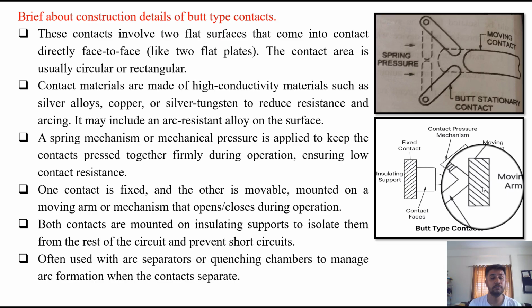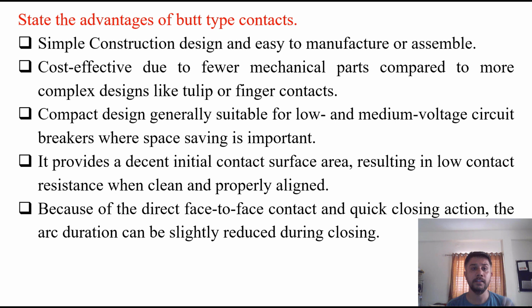Often used with arc separators or quenching chambers to manage arc formation when the contacts are separated. So this is how the butt contacts are used for the circuit breaker, and these are the constructional details. The advantages of butt type contacts. So there are several advantages. Some are listed over here.